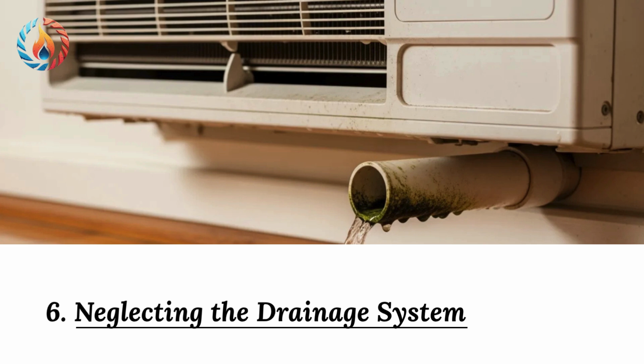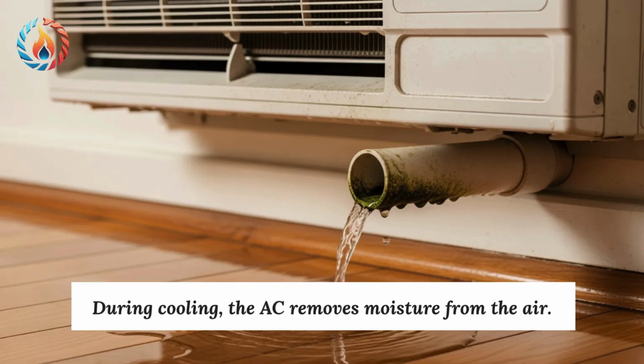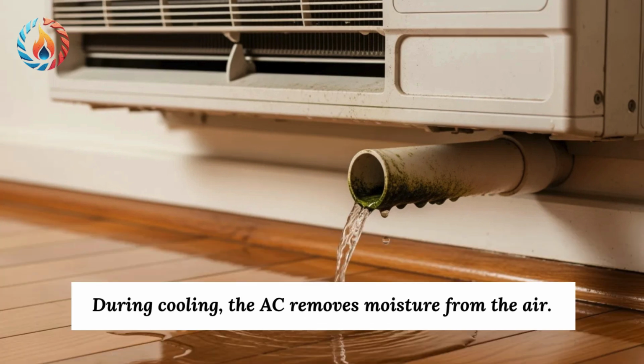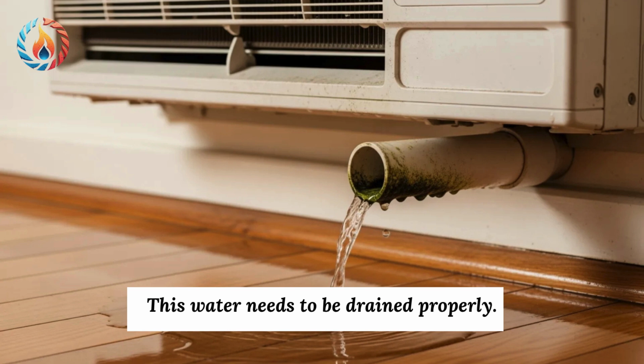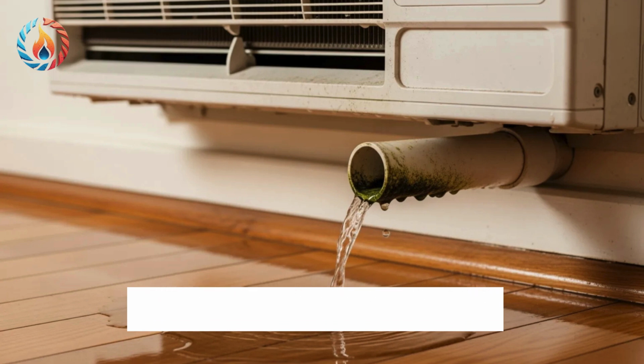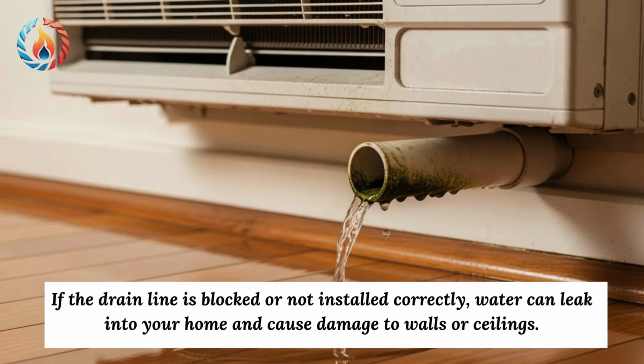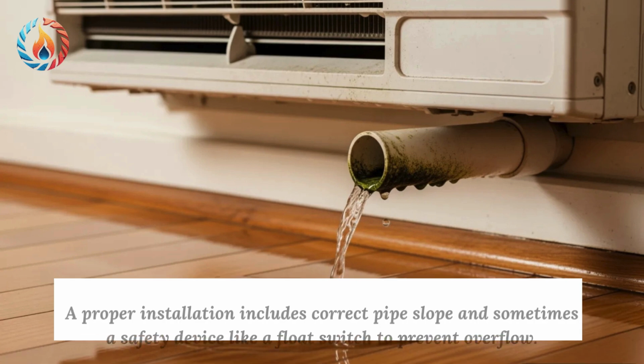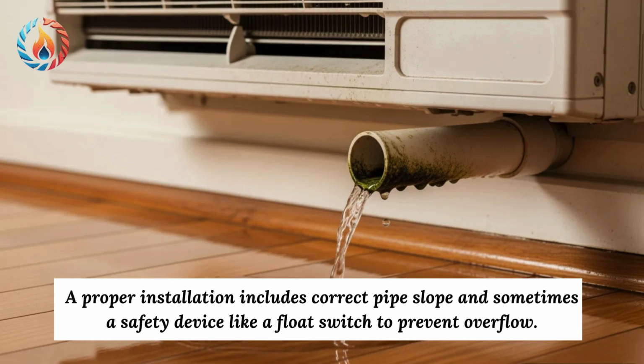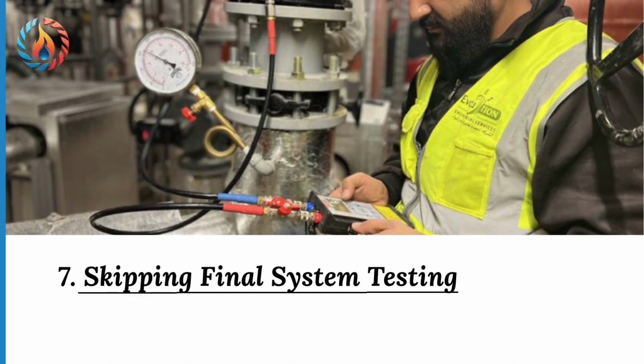6. Neglecting the drainage system. During cooling, the AC removes moisture from the air. This water needs to be drained properly. If the drain line is blocked or not installed correctly, water can leak into your home and cause damage to walls or ceilings. A proper installation includes correct pipe slope and sometimes a safety device like a float switch to prevent overflow. 7. Skipping final system testing.